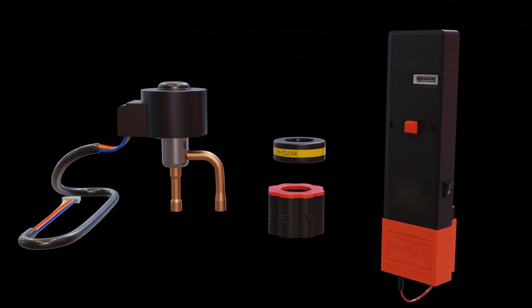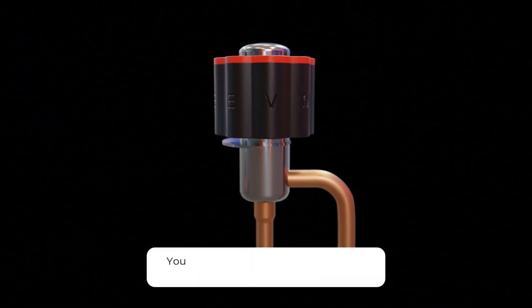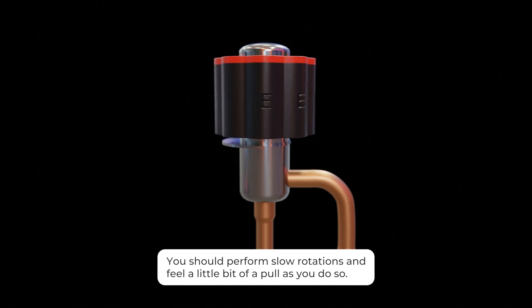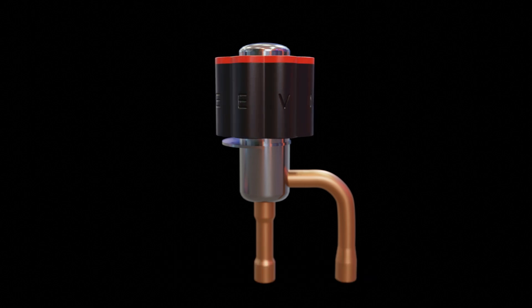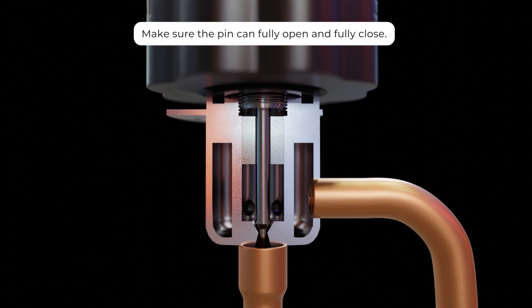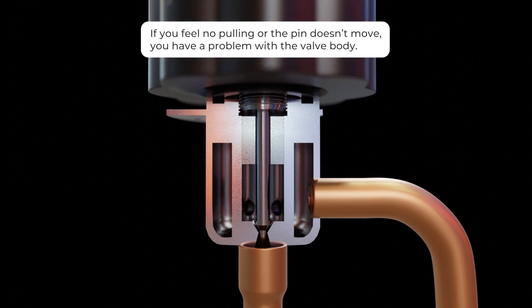If you use a manual actuator, you'll remove the power head and replace it with the actuator. You should perform slow rotations and feel a little bit of pull as you do so. Make sure the pin can fully open and close. If you feel no pulling or the pin doesn't move, you can be sure you have a problem with the valve body.